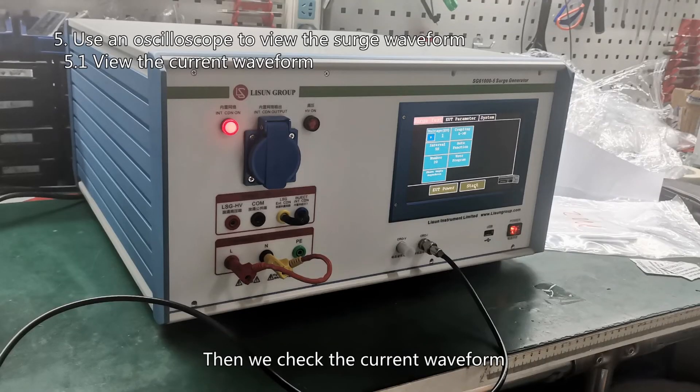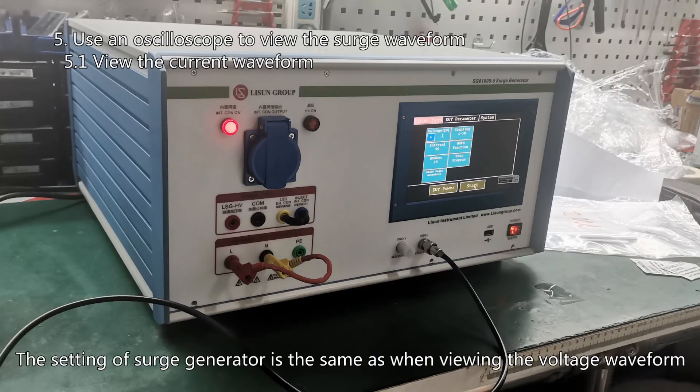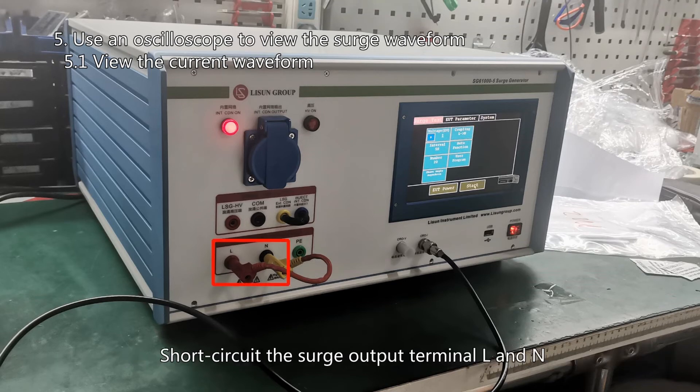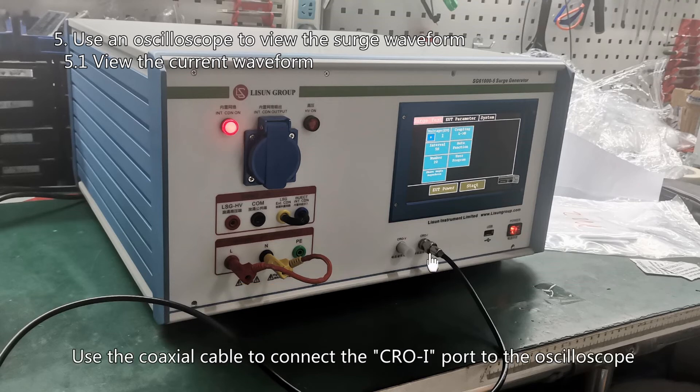Then we check the current waveform. The setting of surge generator is the same as when viewing the voltage waveform. Short-circuit the surge output terminal L and N. Use the coaxial cable to connect the CRO-I port to the oscilloscope.